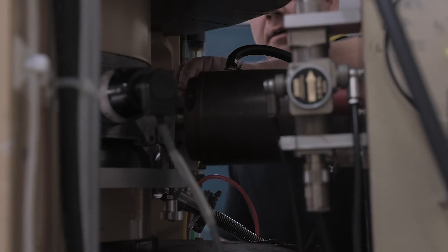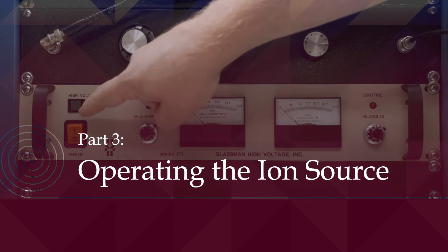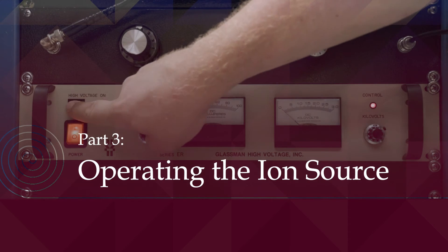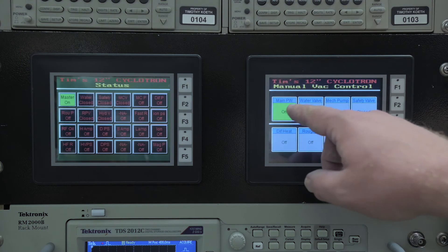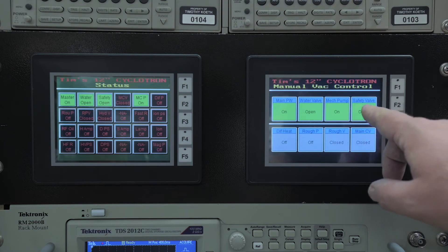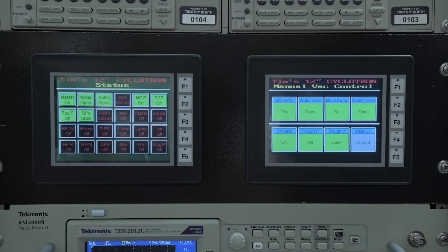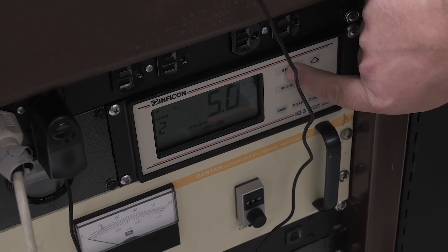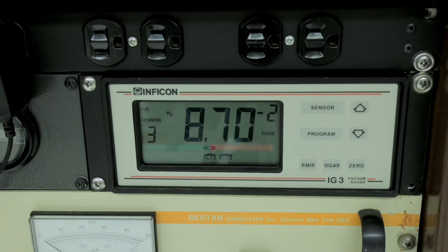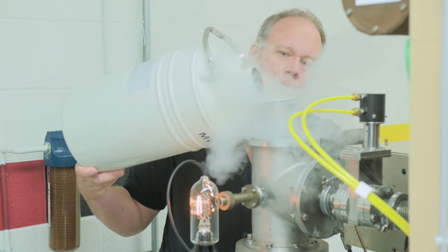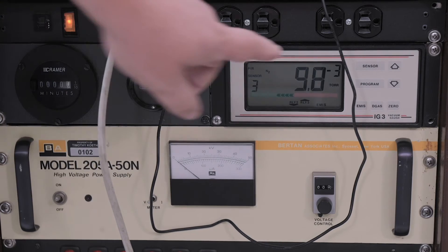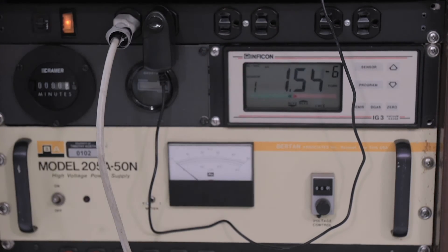Now we are ready to give the ion source a test run. We begin the pump down sequence by roughing the chamber while the diffusion pump heats up. Once the diffusion pump is operating, we valve out the rough pump and valve in the diffusion pump, aiming for an ultimate pressure in the order of 10 to the minus 6 torr range. On a good day, even the high 10 to the minus 7.